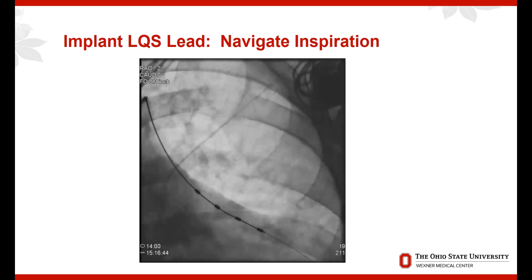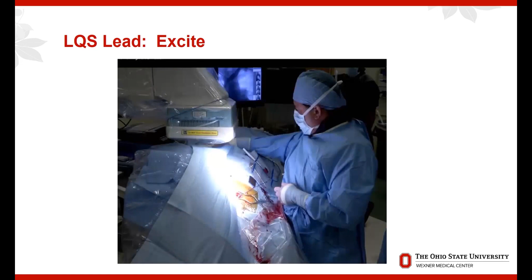We then test capture of the diaphragm. It is important to use only conscious sedation to assure the patient can report what they feel. There are some pain fibers which can be avoided by slight reposition of the lead location. Stimulation should result in a strong, smooth diaphragmatic capture. Typically, capture threshold is between 2 and 5 milliamps.